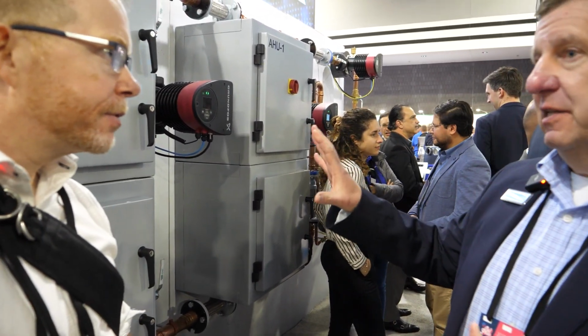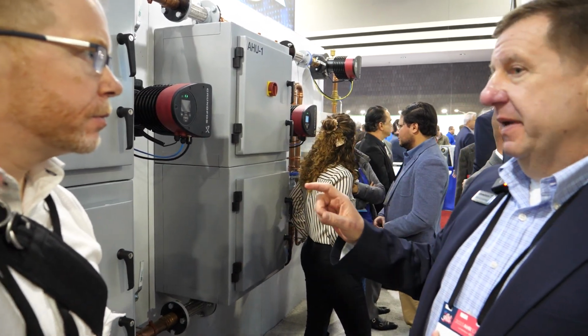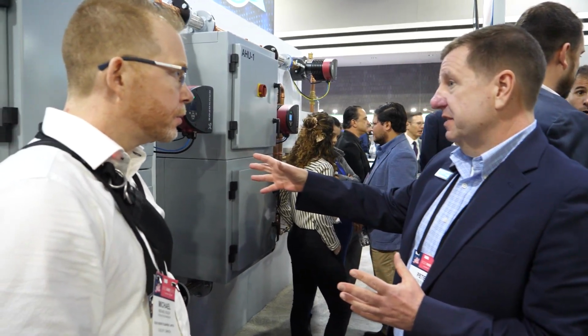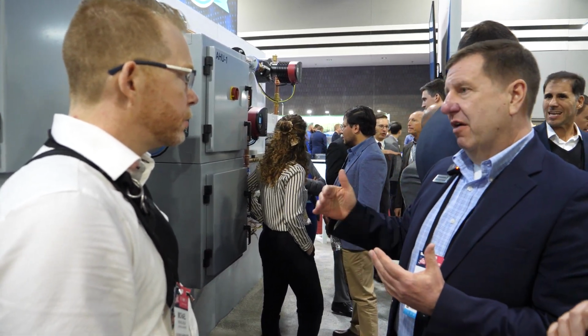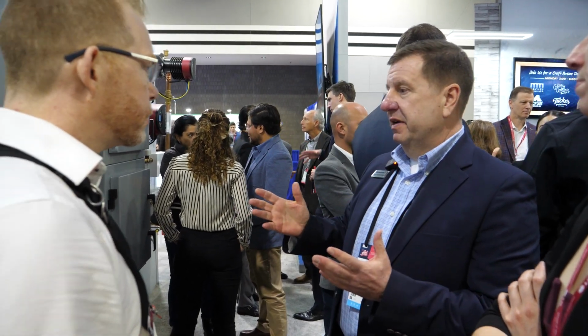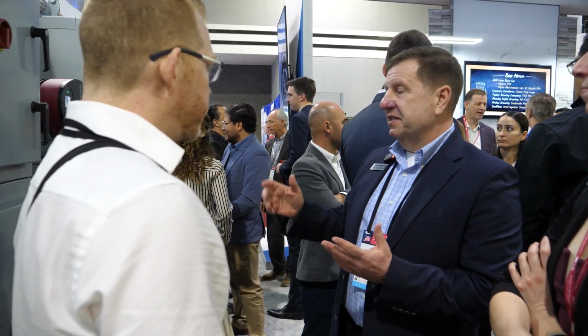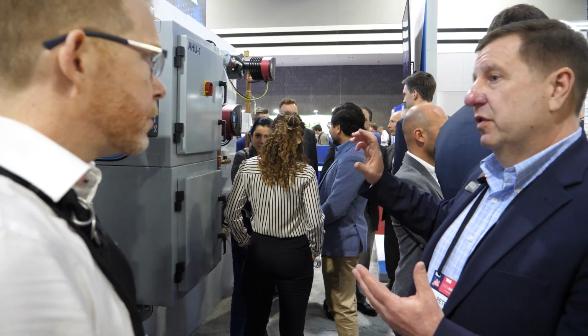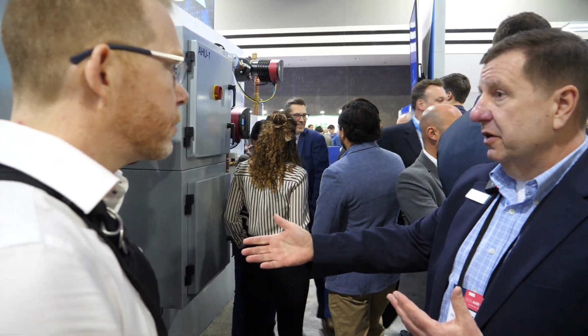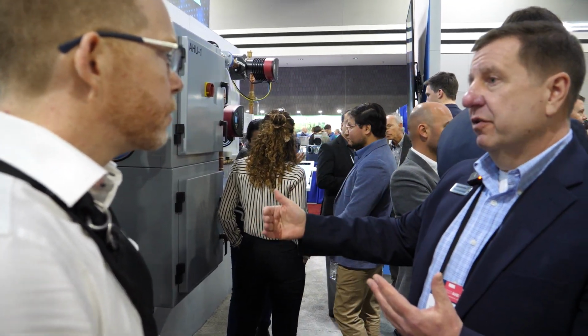Really, this pump is sized for the flow rate for the load. We picked the head to overcome the resistance this pump will have for this specific load. So we come out to the pump, give it a set point, and enable what we call flow limit, which is essentially like a governor for the pump. So if we've sized it for 100 gallons a minute for this load, even though it's capable of pumping 140-150 gallons a minute at the far right of its curve, we electronically tell the pump it is a 100 gallon a minute pump. It will never pump more than that. So we've eliminated another reason for having a balancing device. Now it's electronically commissioned for this particular air handling unit. No matter what happens down the line, even if you get fouling in the coils within the terminal unit, the pump will adapt and always provide the perfect flow at the right pressure.